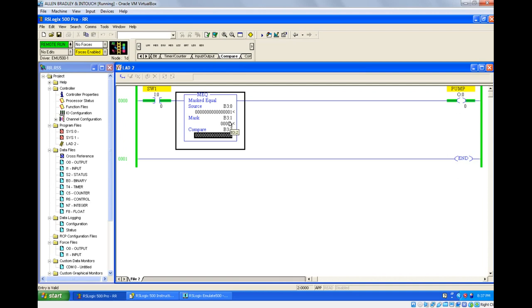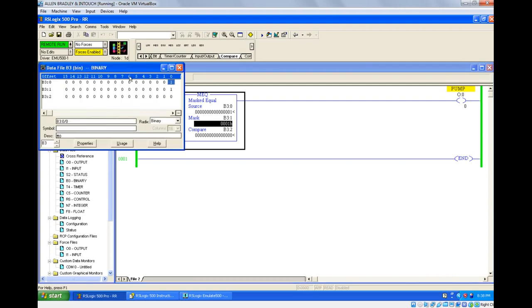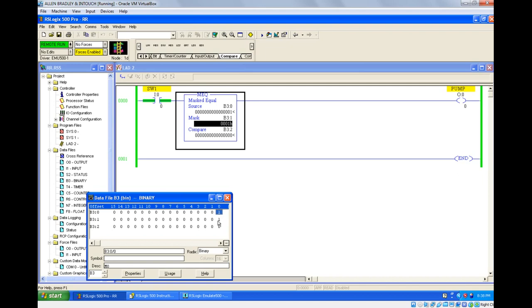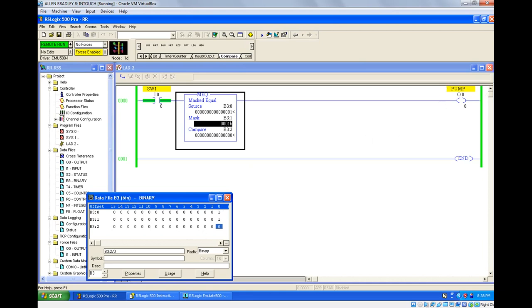If you want to get the exact output — whether it is true or false — you need to activate your mask bit. I am activating the mask bit by giving 1. Now the pump is off. The mask is 16 bits wide; the first bit is on, so it will compare the first bit of B3:0 with the first bit of B3:2. If both are equal it gives output; if not equal, it does not give output. Now the pump is off because 1 is not equal to 0.